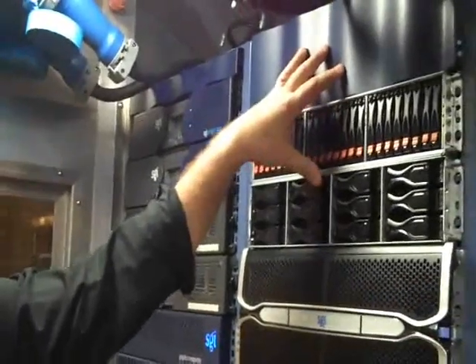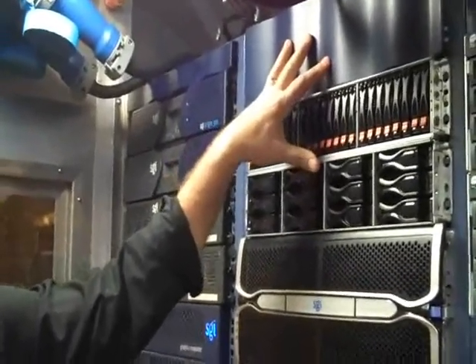And how high are the racks? Somewhat different. They're not standard. So these racks are, again, the show unit. The production unit is 51U racks, and we provide 35 kW of cooling with outside air and a garden hose, which we'll show you shortly, to those racks. So 51U's standard. If you're going to roll in your racks, that provides you 89.25 inches of headroom to roll in your own racks. And we supply 35 kW of power to each one of the rack locations.